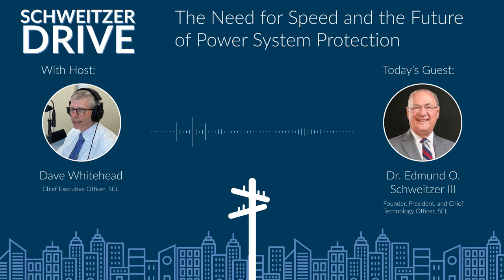Let's suppose you have a transmission line, and it's not faulted, but there's a thunderstorm in the area, and there's a line-to-ground strike not involving the power system. So here comes a traveling wave from that current impulse of the lightning strike somewhere away. It propagates over and is picked up by the antenna, if you will, of the transmission line, and we can detect that at both ends of the transmission line, and we will see that there was a traveling wave present.